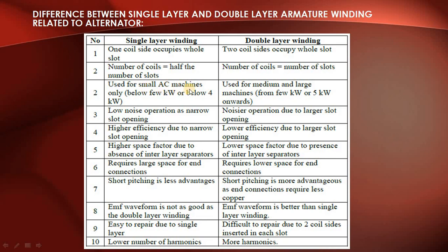Third difference: single layer winding is used for small AC machines only, that is below 2 kilowatts. Double layer winding is used for medium and large machines, above 5 kilowatts. Fourth difference: single layer has low noise operation due to narrow slot opening, whereas double layer has noisier operation due to larger slot opening.